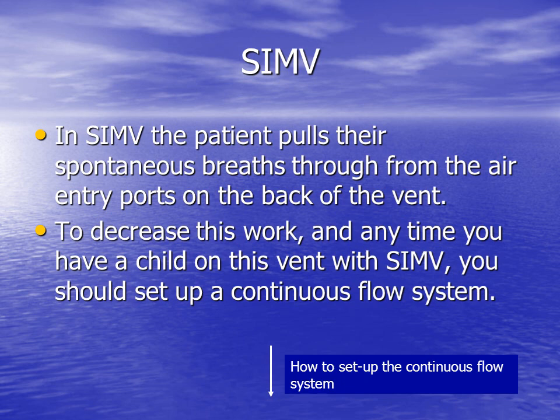In SIMV, if you're using the high-pressure O2 connection and you're not also purchasing and using their special O2 sensor, then the patient is only receiving oxygen on the set breaths and not on their spontaneous breaths. And the spontaneous breaths the patient is able to take on SIMV are actually breaths that they themselves pull through the vent, through the circuit, through the air entry ports on the back. These are not pressure-supported breaths, and as you might imagine, there's a considerable work of breathing involved in pulling those breaths. If you wish to make it easier for the patient to access these breaths, or if you have a pediatric patient, you should set up a continuous flow system.